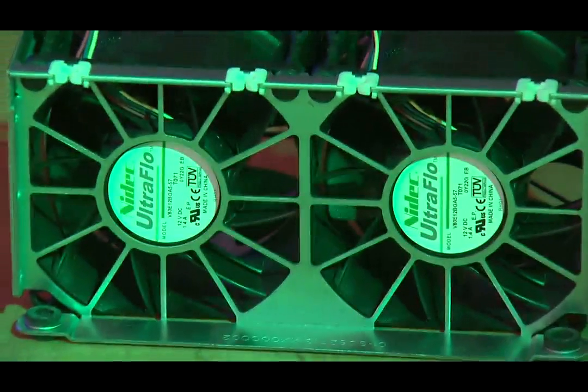The traditional approach of normal air-cooled data centers wastes large quantities of energy running air handling equipment. It's estimated that 20% of IT load is from internal fans, and a further 65% is used in air handling and cooling on a data center level.